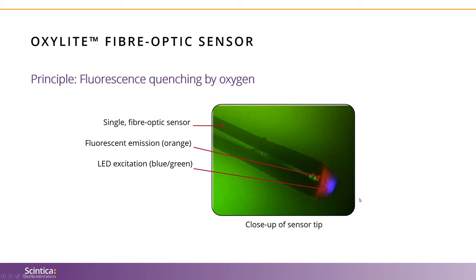So how exactly do the OxyLite systems work? The OxyLite is an optical device based upon the principle that the presence of molecular dissolved oxygen in tissues or fluids can terminate or quench light emitted by a fluorescent compound dye. The quenching of the fluorescent light is proportional to the PO2 in the vicinity of the dye. When that dye is illuminated or excited with light from the monitor, it fluoresces. The fluorescent light is then returned to the monitor using the same optical fiber, and the signal processor determines the fluorescent decay time. From this, the corresponding PO2 is derived. As PO2 in the vicinity of the sensing tip decreases, the extent of the quenching decreases and fluorescence decay time increases. The OxyLite monitors perform automatic temperature compensation and generate a continuous readout of temperature when combined oxygen-temperature sensors are in use.